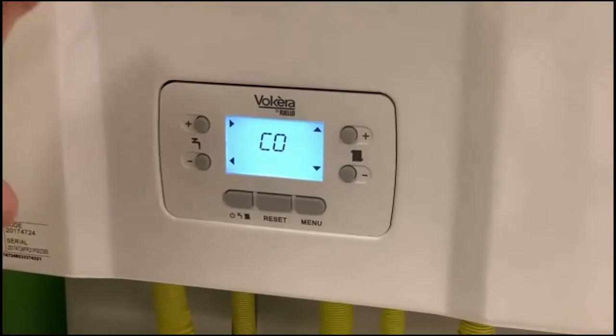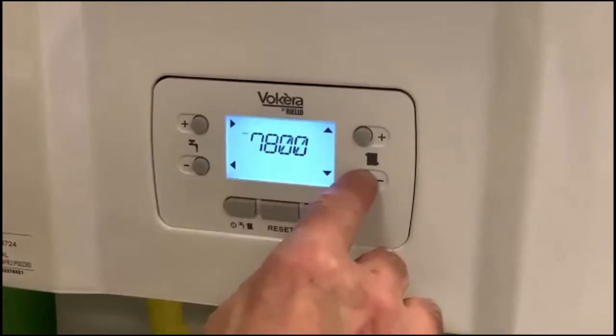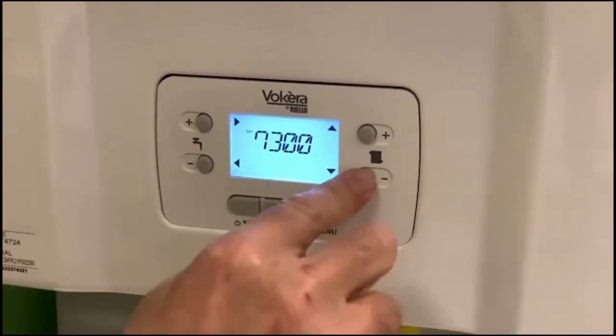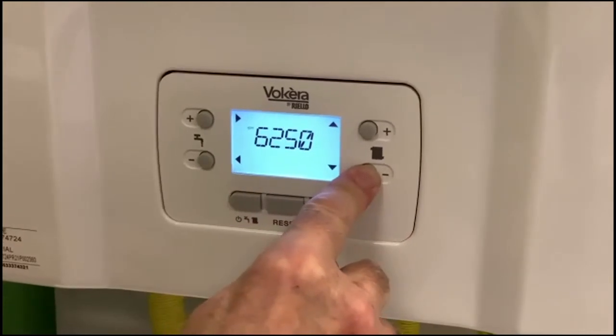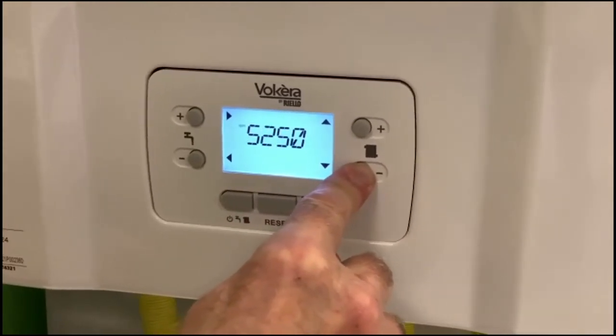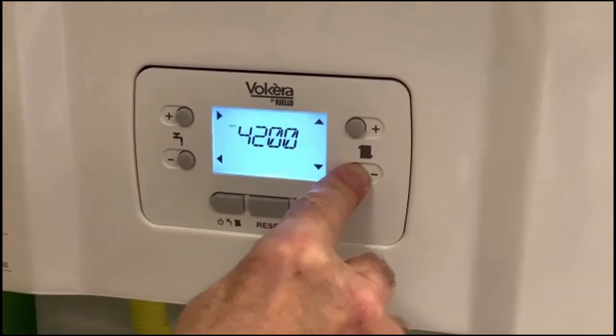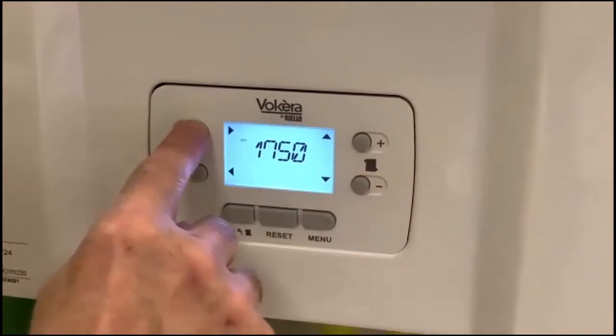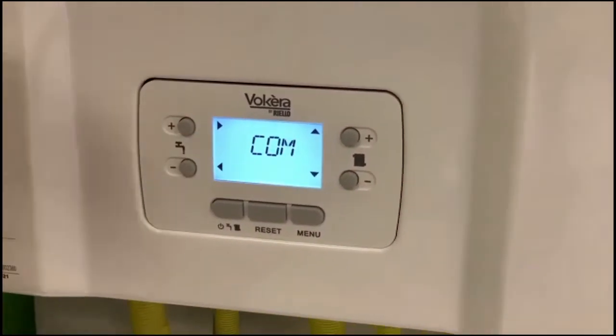Take a reading with your analyzer, jot it down. Now drop the fan speed by pressing the minus button on the right to minimum. It won't go beyond minimum because that's preset on the board. Press to confirm. The fan speed will drop down. Take a reading. If you're within 0.2% CO2 percentage, you're done.